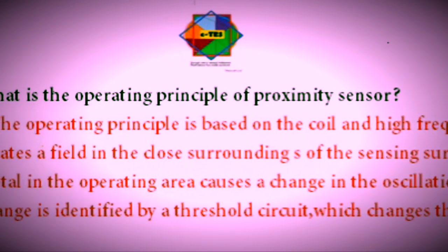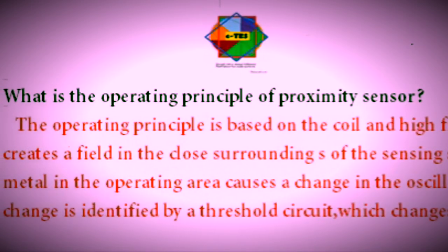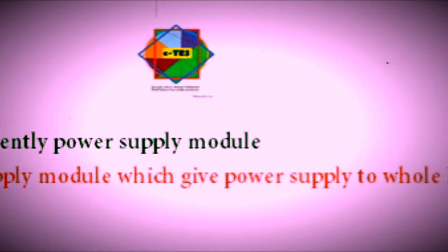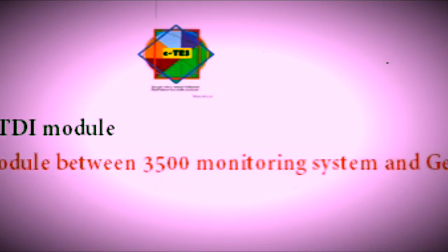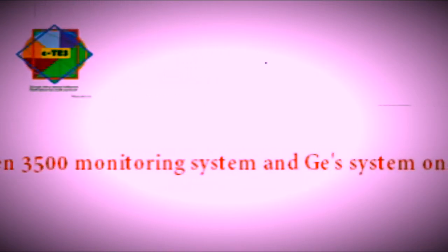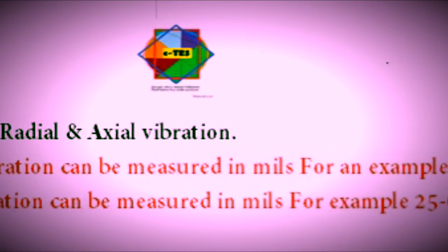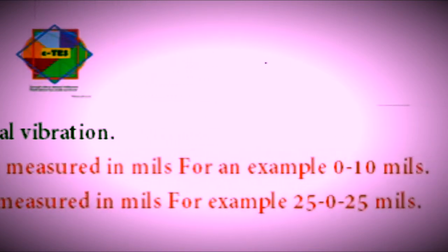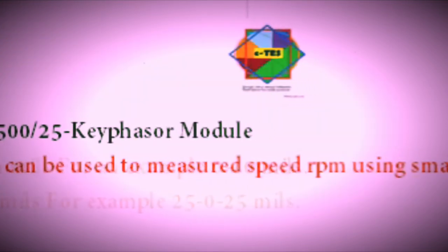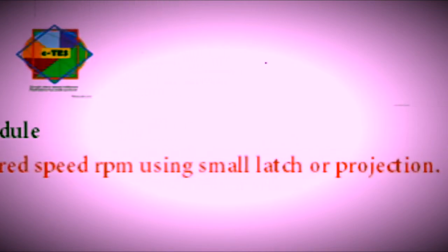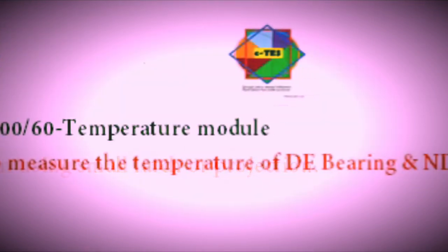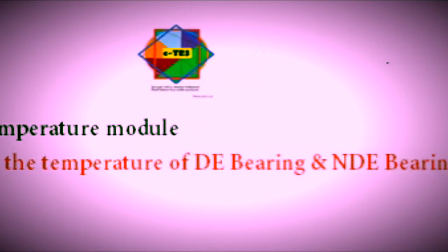The principle is the inductive proximity principle with change in amplitude. The 3500/15 is the power module used in Bently Nevada. The 3500/22M is a TDI system, an interface module. The 3500/40 is used for radial as well as axial vibration. The 3500/25 is a keyphasor, used to measure speed. The 3500/60 is a temperature module used to measure temperature.